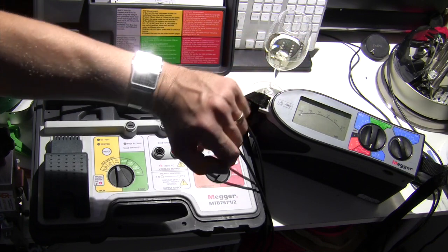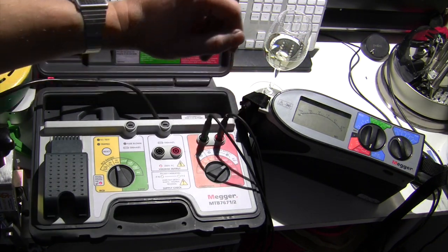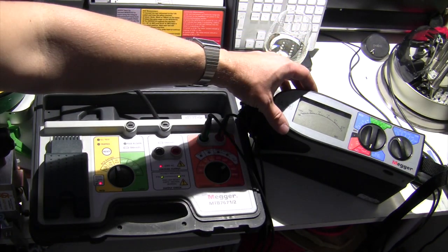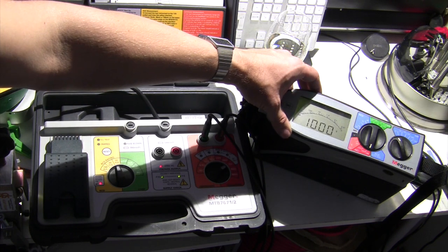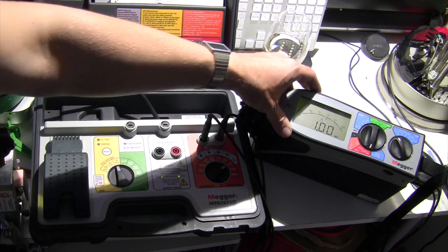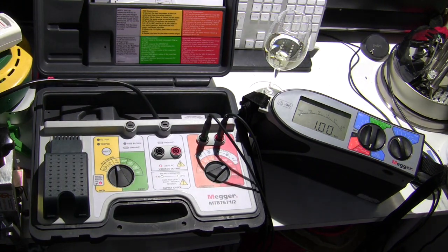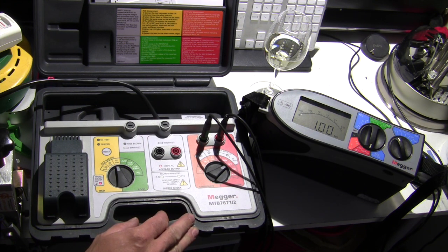Now this particular tester is going to sound a bit of an alarm when I select the kilovolt range. The Fluke doesn't, but this one does. It just beeps a few times before it actually does the test. It says, are you sure you want to squirt 1000 volts into this thing? And in this case, yes we do, and we get the reading we expect to get, which is 1.00.